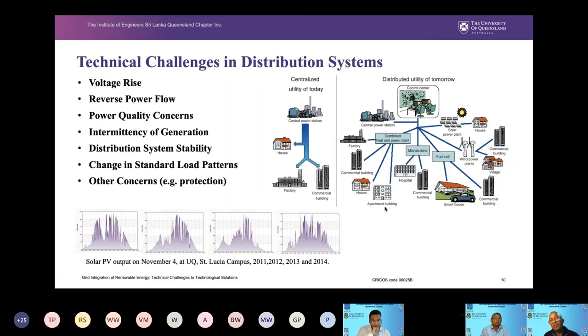So another problem at the distribution system level is the intermittency created by the large-scale, massive integration of rooftop PV. Just to give you an idea, I have highlighted and captured this real waveform, the power versus time, from UQ solar. You can see how badly this power can vary, from a maximum value to a very low value. This could happen due to a change in the solar radiance. The intermittency of generation is not only a problem in the distribution system, but also a huge problem in the transmission system collectively as well. So that means we have to have certain generators ramp up and take that slack to supply the loads uninterrupted without any problem.